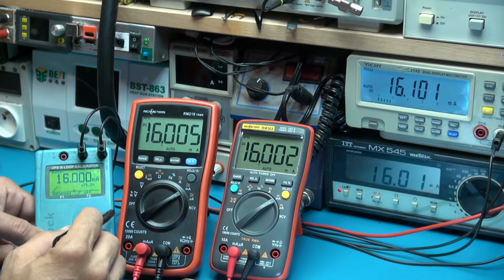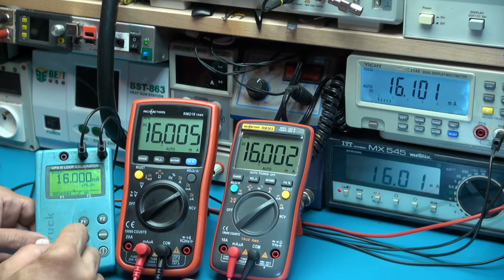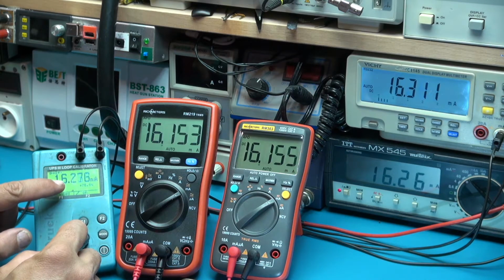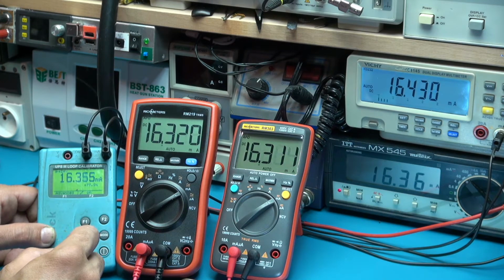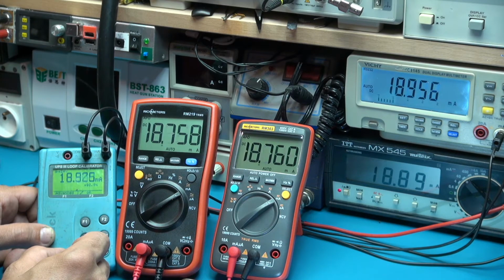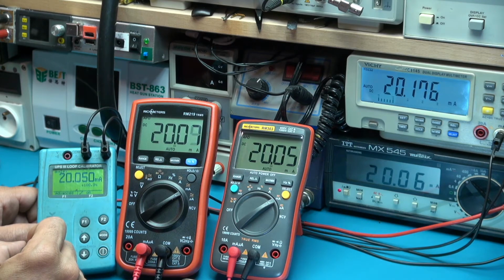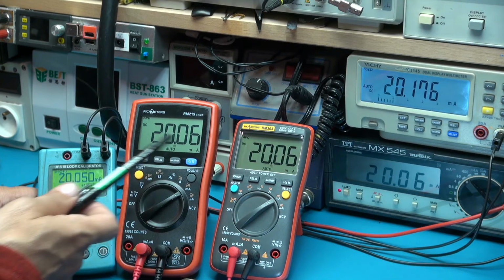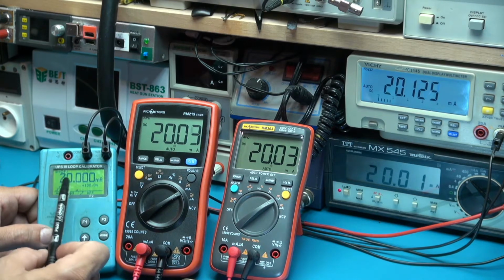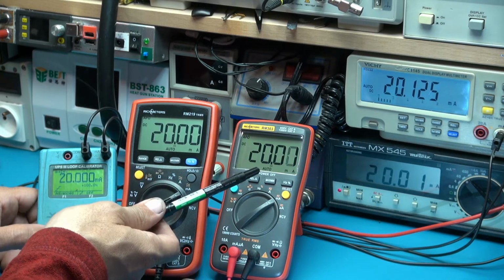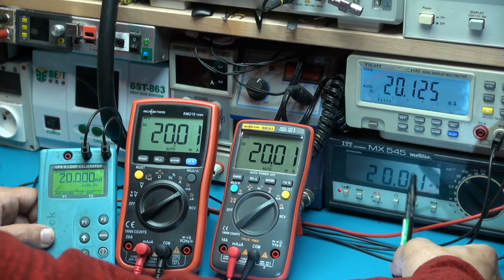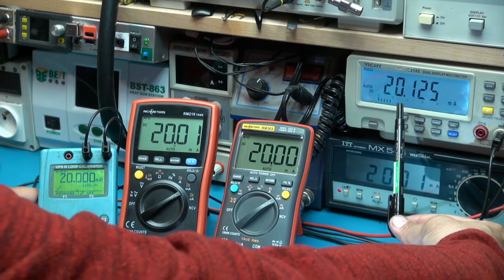So here we are going to choose the step-by-step function, and you can see the current is rising step by step until we reach the 19,000 points on those multimeters, and you will see the maximum reading before toggling to a higher value. And you can see here we are approaching the... okay, you can see now you lose one digit, and you will have now 20 milliamp. It's very accurate actually. You will have also here a little positive offset, and here a very important offset.